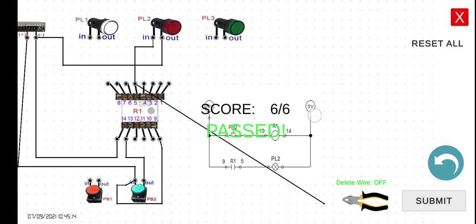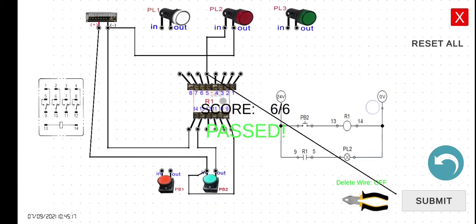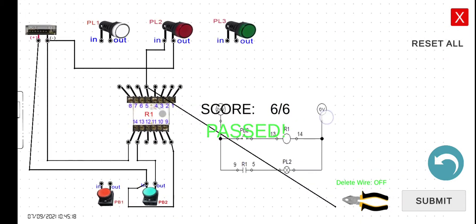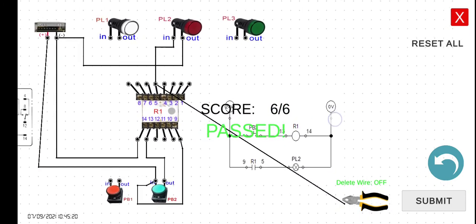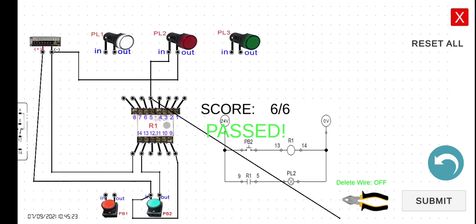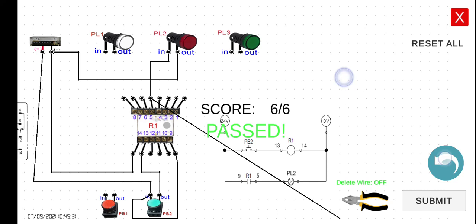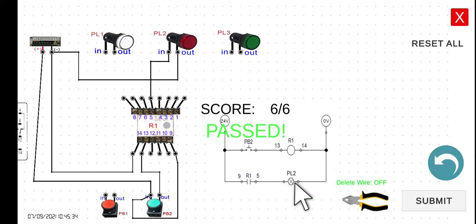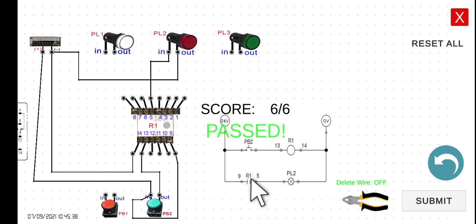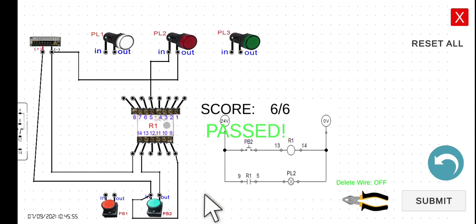So it means we got all the wires connected correctly. Now let's try to simulate this one. If we press this PB2, we can expect, or we should expect, that this R1 will be energized. So this will be indicated by this lamp around here. And then, at the same time, this PL2 will turn on because this will close here. Let's try to click the PB2. Okay, on, and then if I'm going to release this push button, it will turn off. Click again, on, release, off. So see you in the next lecture.